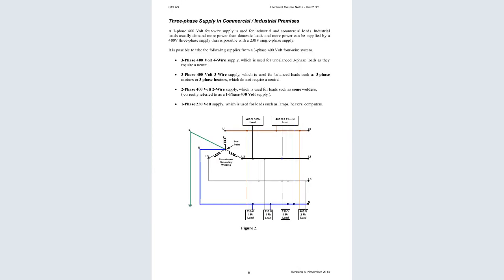Phase means live. When I talk of a phase, it means live. So for a 3-phase, it has 3 live wires. Are we together with that? Yes. For a three-phase, we mean we have 3 live wires. It is called a three-phase because it has 3 live wires. And when we have a two-phase, it means we have 2 live wires. When it is called a single phase or one phase, it means we have 1 live wire. So for this supply system, it has 3 live wires.